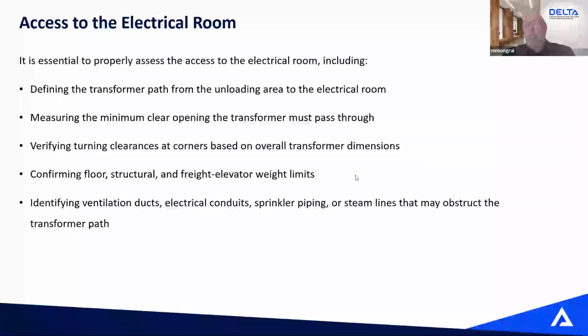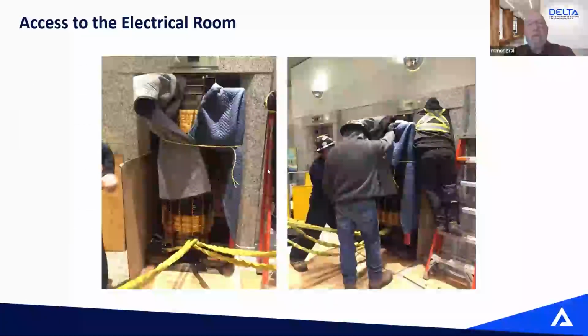We need to make sure about weight limitation of the floor, structural slab, freight elevator weight limit, freight elevator door size. We need to know all of that. And also traps such as ventilation ducts, electrical conduits, sprinkler piping, steam lines. We've seen all kinds of stuff over the years, so it's important that we know exactly where we need to go to bring that transformer inside the electrical room, so that when we deliver the transformer, there's no surprise, there's no hiccups.